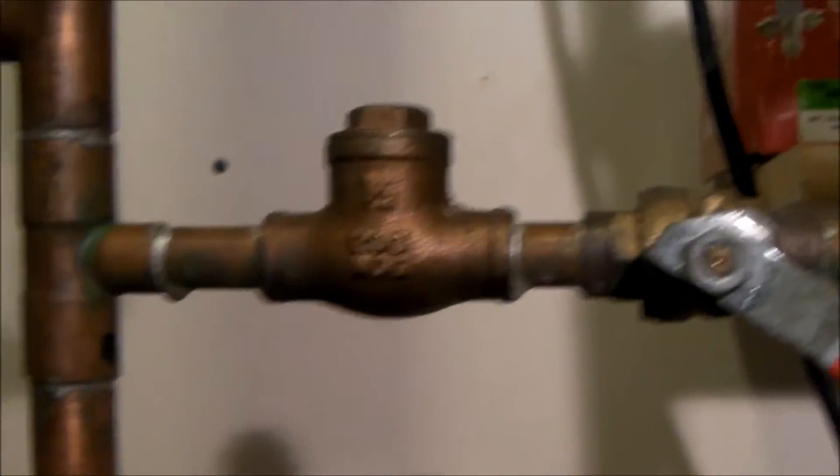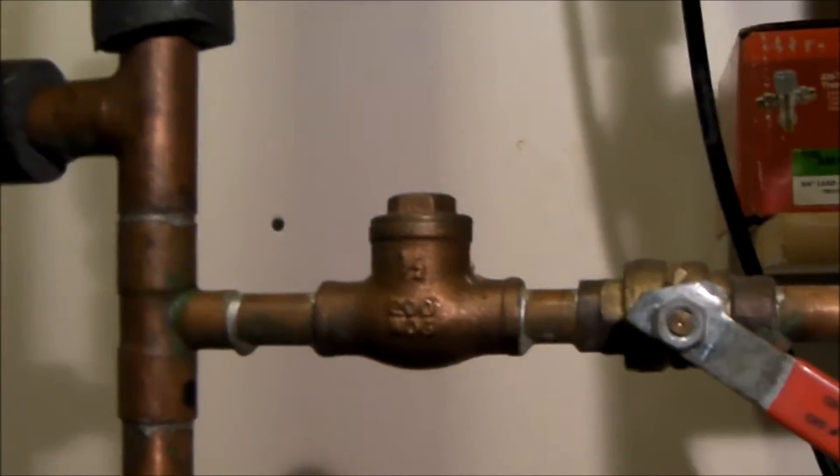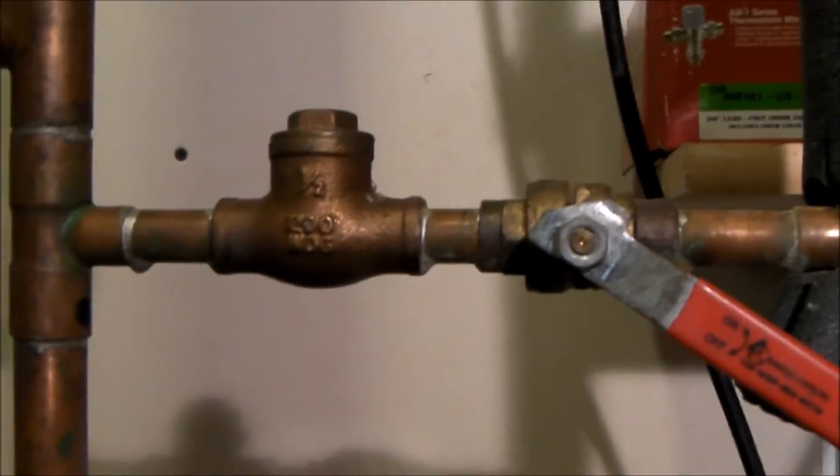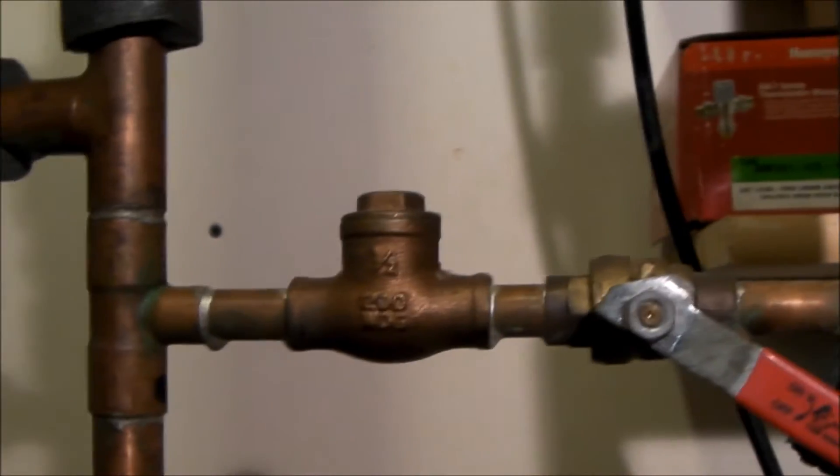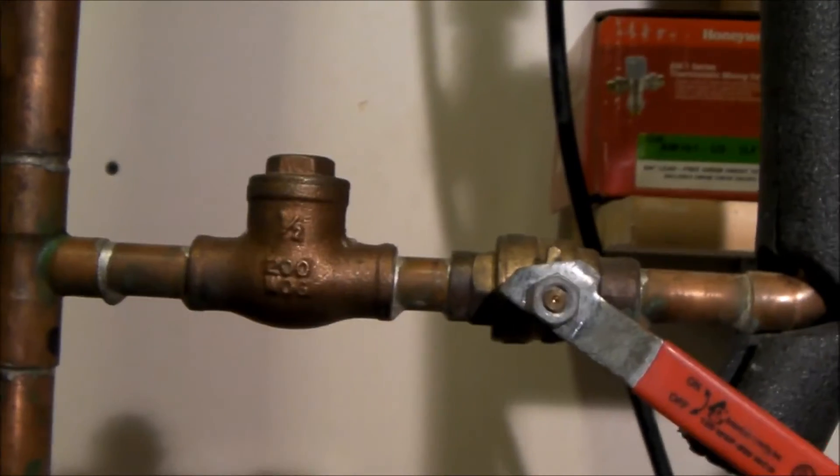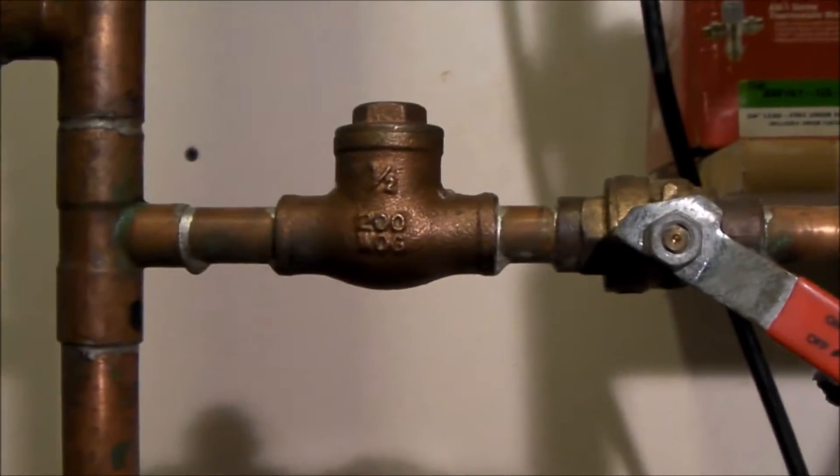So I've tried to remove the cap on this and I put quite a bit of force on it. I don't want to break these solder joints by creating more of a problem. So I'm just going to unsweat this, drop a new valve in, they're pretty cheap, and then we'll dissect this check valve and see whether it's really failed.